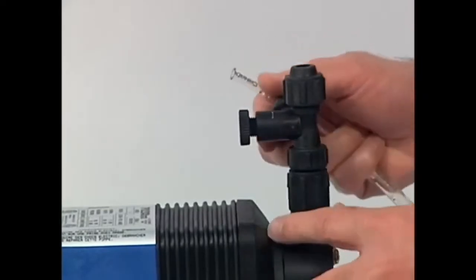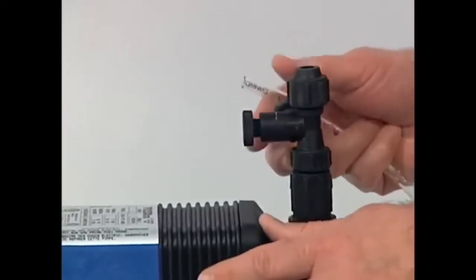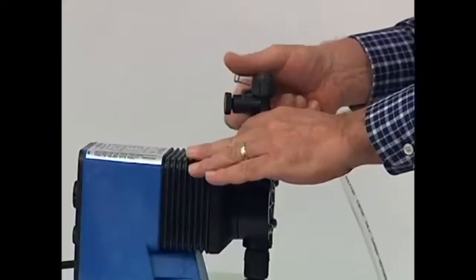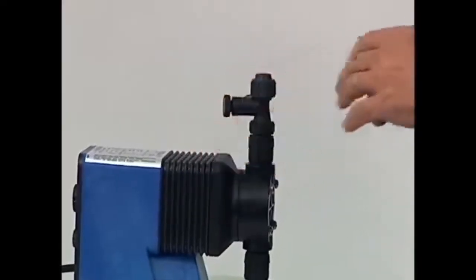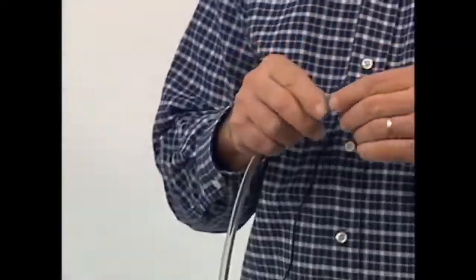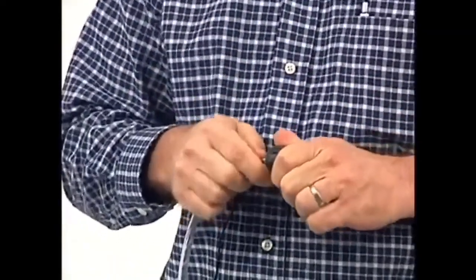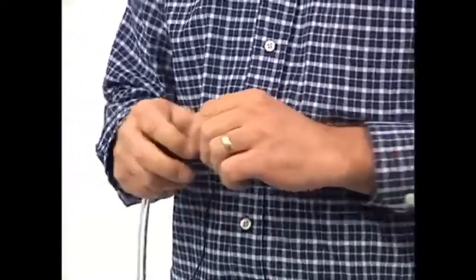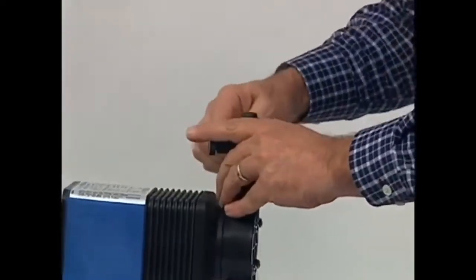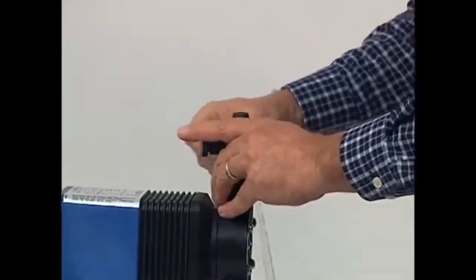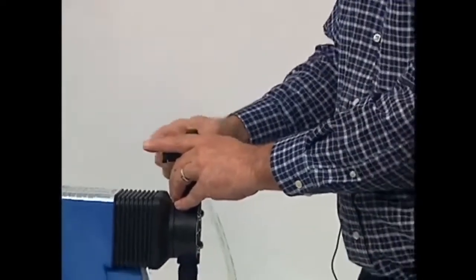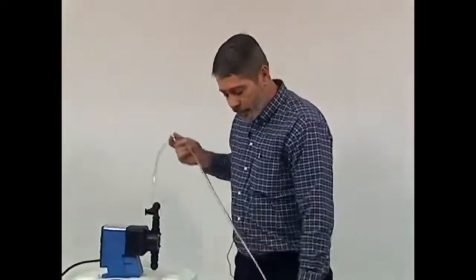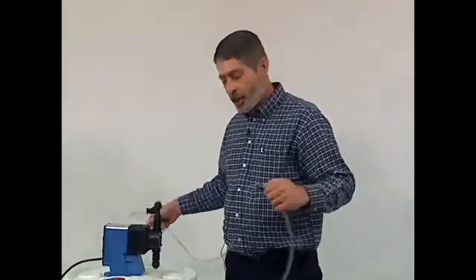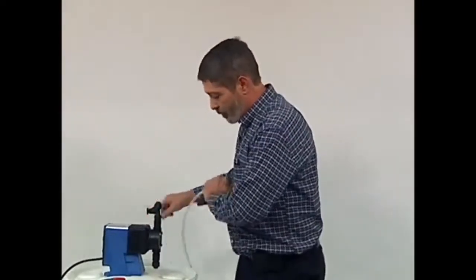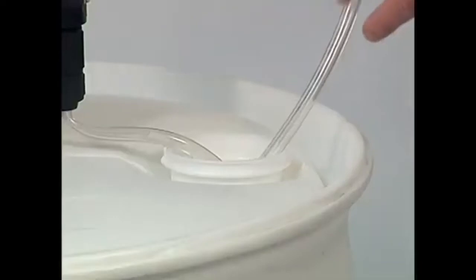Here on top of our pump we have a priming valve. The priming valve will have 2 discharge points, one that is the pressure side back to your system, and one that will always be atmospheric, that is your return to container line. Return to container line is important because when we prime a pump, we normally prime against atmospheric pressure, which we can't do if we're pumping against the system pressure. So the other low pressure clear line can be used to return any excess chemical back to the container you're pumping it from for priming purposes.